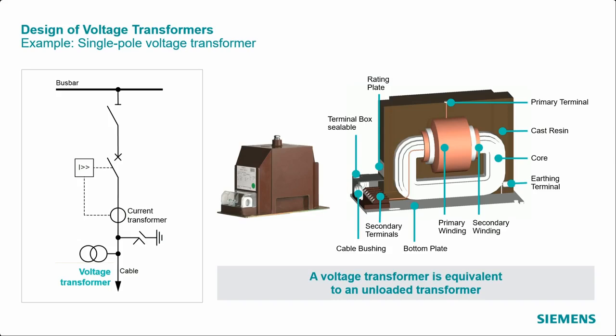voltage transformer, or PT for potential transformer. Also here, usually 3 are used in one panel, 1 per phase, but not always. Similar to the CTs, it all depends on the design of the protection system. Let's break down its components. The primary terminal is connected directly to the high voltage. Single-pole VTs have only one primary terminal. The secondary terminals are connected to the measurement or protective devices and provide a scaled-down version of the voltage in the primary circuit. The secondary can have multiple terminals depending on the requirements for connection and the provision for different measurement ranges or for redundancy in measurement.